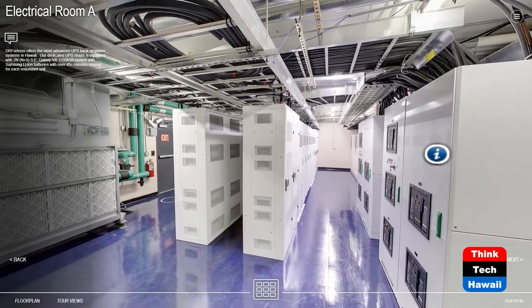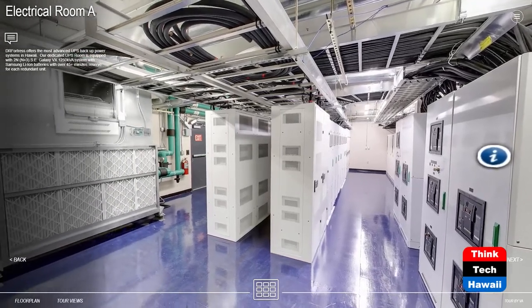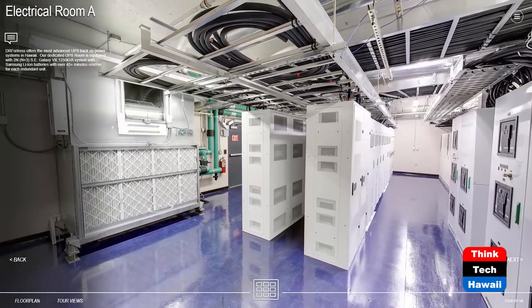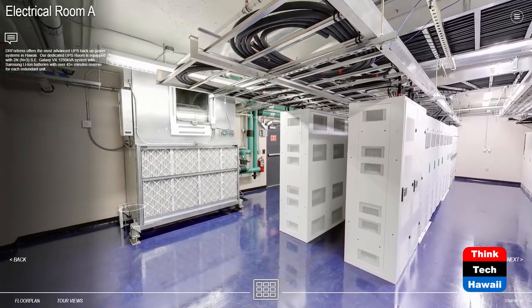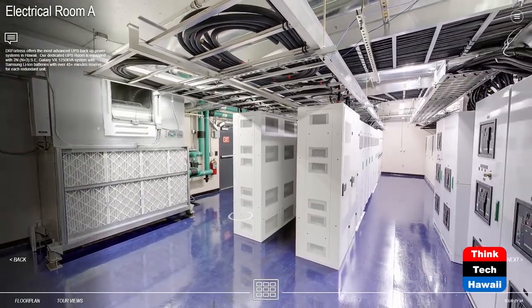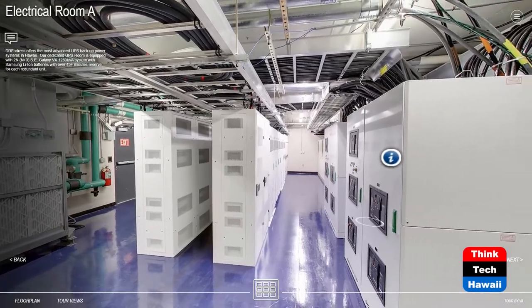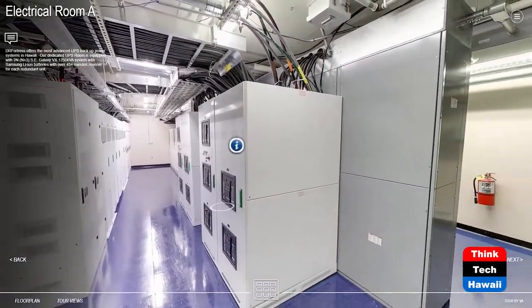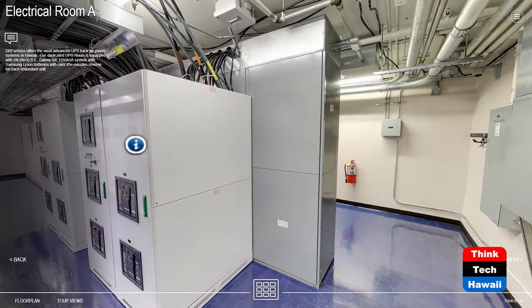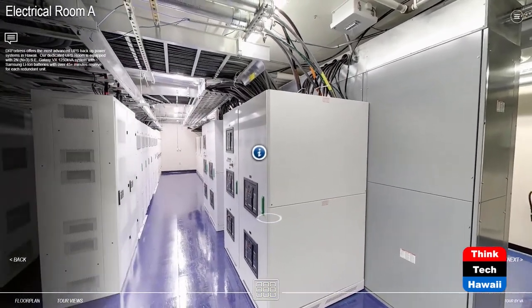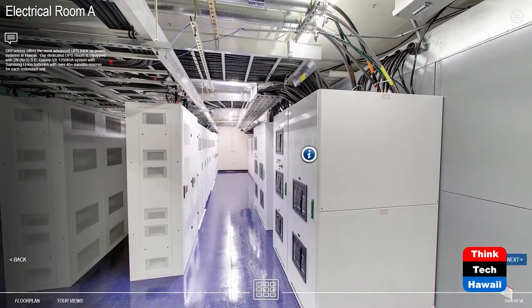This is a new lithium ion UPS system. It's a 1.25 megawatt A and B system. We brought that in. It's what cleans all the power to the customers. And if we were to lose power, it'll hold the power for the customers for about 45 minutes. After about 13 seconds, the generators turn on, synchronize, and refeed the facility. But we have it just in case something happens, for a longer ride through.